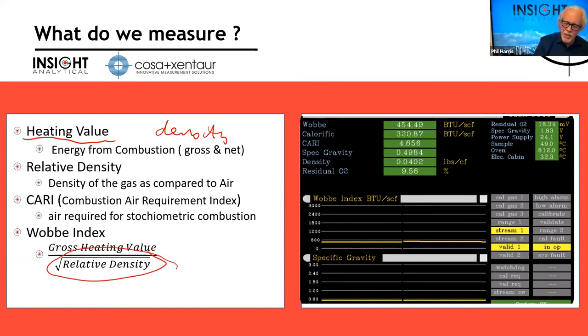And the reason this comes into play is, often there's some kind of flow controlling device that controls the flow of fuel and of air into the burner. The air doesn't change composition, but when the fuel does, the amount of flow that goes through the orifice changes with the density of the fuel. So we want to know how many BTUs, how much energy is in the fuel, the heating value. And then we also want to know the density, because that lets us figure out how to control how much air I'm going to need. Changes in the fuel density are going to change the fuel flow rate into the burner, as well as change the heating value. So I need to adjust my burn air for the change in chemical composition, how much air it needs to burn all that fuel, and the change in flow rate into the burner. So Wobbe Index is the control variable that best allows us to do that.